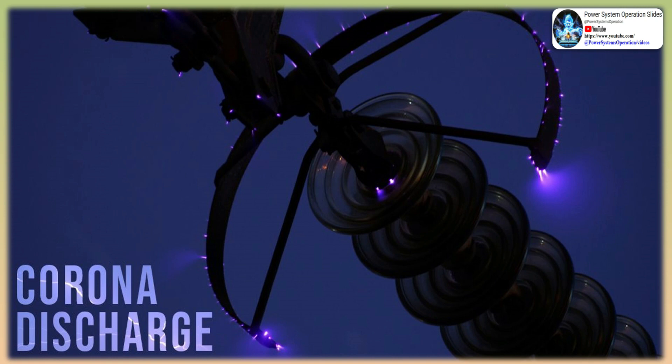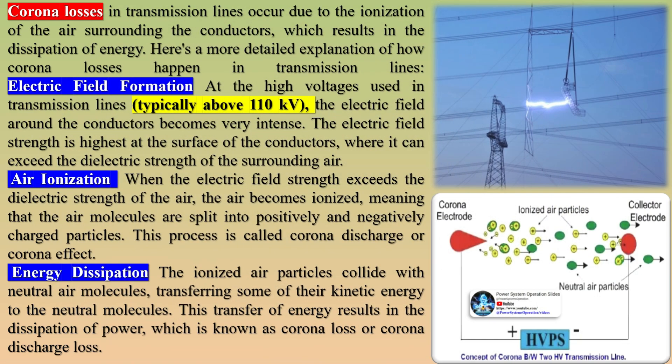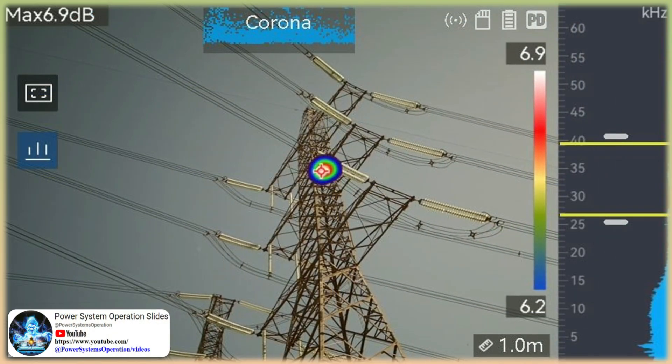Disadvantages of corona losses: Energy losses — corona losses result in the conversion of electrical energy into heat and light, leading to reduced efficiency in the transmission system and higher operating costs. Insulation damage — intense corona discharge can cause degradation and erosion of insulator surfaces, compromising their effectiveness and increasing the risk of flashover, which can lead to power outages and equipment damage. A non-sinusoidal voltage drop occurs in the transmission line due to non-sinusoidal corona current, causing interference with neighboring communication circuits. Ozone gas is produced due to the formation of corona, which chemically reacts with the conductor and causes corrosion.